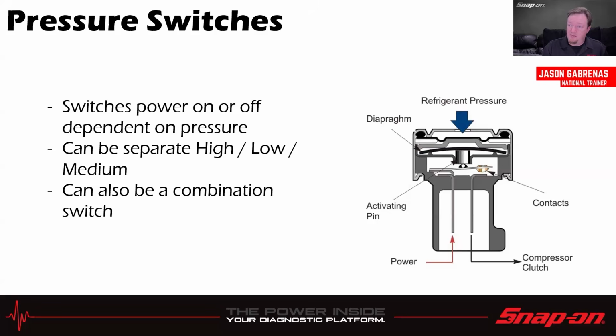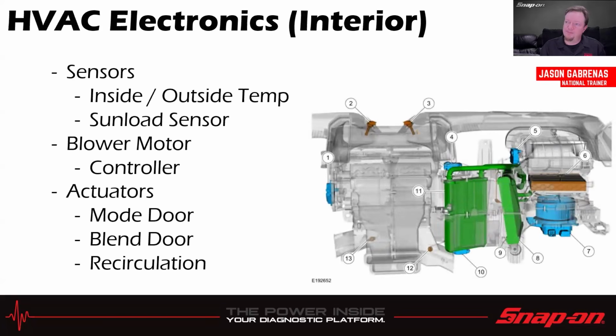Then we have pressure switches. They just power on and off depending on pressure, sending a simple signal on or off. Can be separate high, low, or medium, or a combination switch that does multiple. Basically the pressure comes in, pushes down on the diaphragm, and when it overcomes the diaphragm at a certain pressure, it closes the contacts and sends power out to the clutch. The simplest ones just turn the clutch on and off. Some more advanced, sophisticated ones send data back to the computer, which controls it that way. It just depends on the manufacturer.